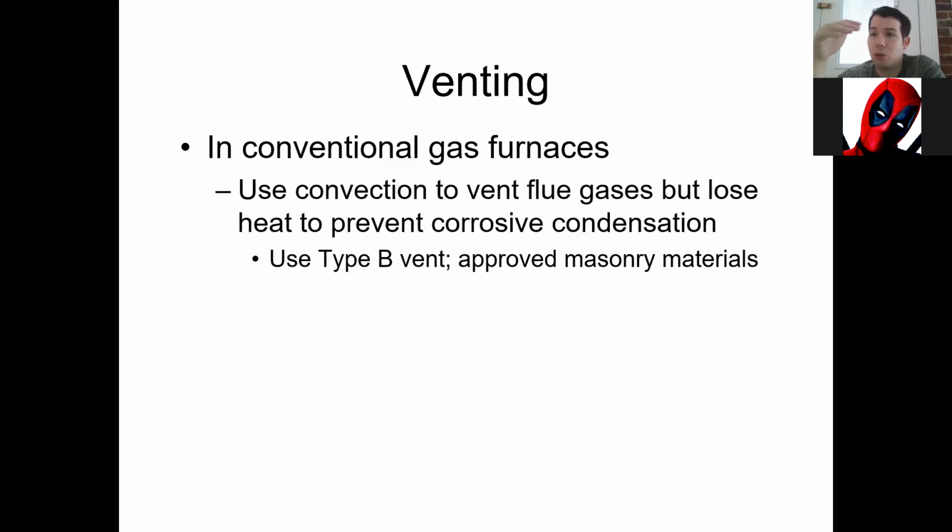Most places make it so that it's no longer up to code if it vents directly through a chimney, which means it just uses the same brick housing that you would for a fire to escape flue gases. The problem is that chimneys and brick are great for getting flue gases out of natural firewood fires, which burn extremely hot. Those are massively hot gases coming off a wood fire.